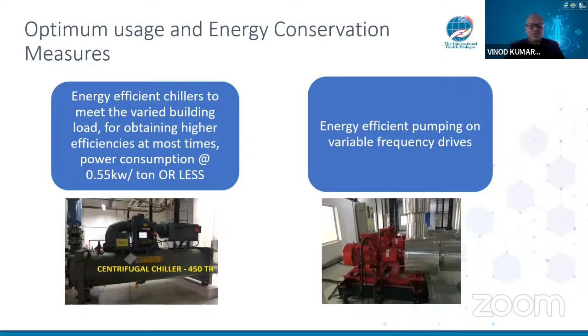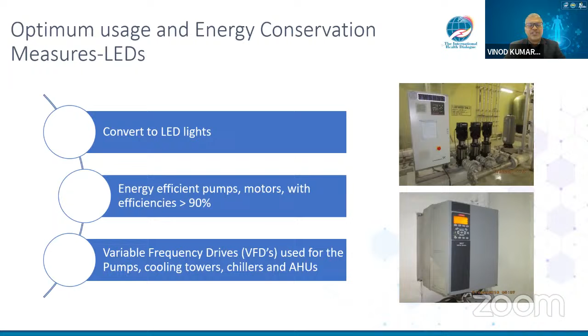Coming to the other energy conservation measures you can look at: convert to LED lights, and select motors which are more efficient, with efficiencies above 90%. We can classify the motors into IE2, IE3, IE4 categories. We also have EC motors nowadays, which are the most efficient motors currently in the market. So look at options where you upgrade your major systems with highly efficient motors, which will definitely bring large power savings. And I did mention variable frequency drives. For systems which pump water, make sure that you have hydropneumatic systems.